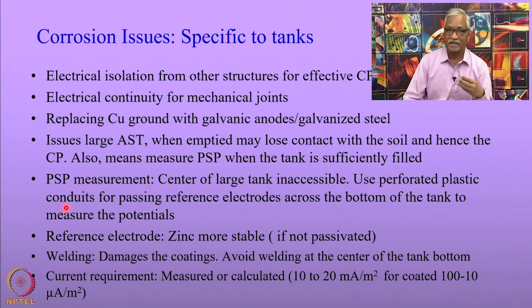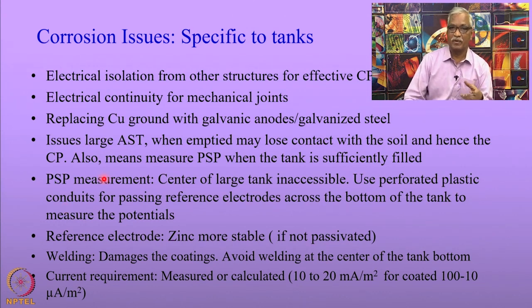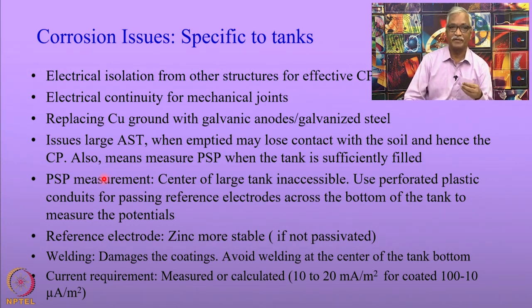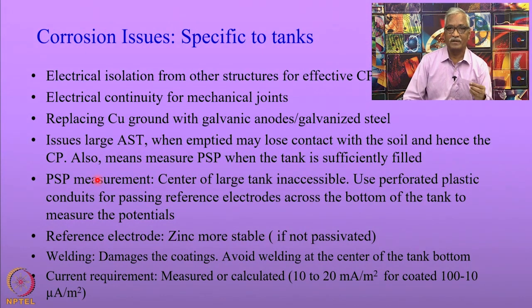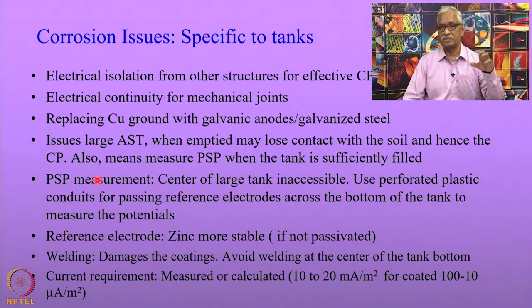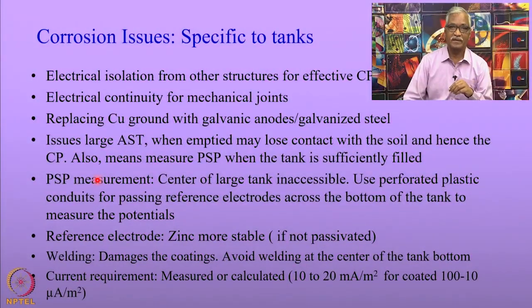Measuring potentials of the structure toward the center of the bottom of the tank is always a difficult issue. In order to do this, people use perforated plastic conduits through which the reference electrodes are passed across the bottom of the tank to measure the potentials.